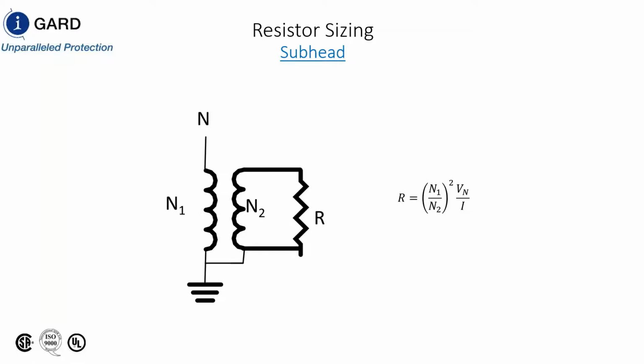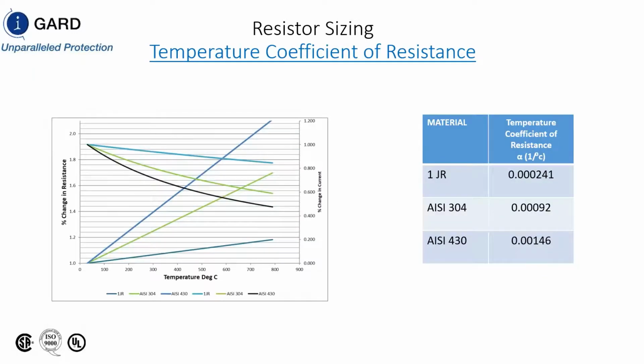Same thing with this particular scheme, and you can use this scheme or the resistor scheme, it doesn't matter. There's one advantage, or slight advantage, in that this particular scheme may take less room, but it's not really relevant in this particular case. What is important is that the codes have changed in recent years.